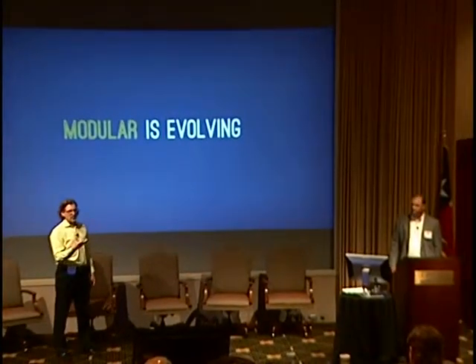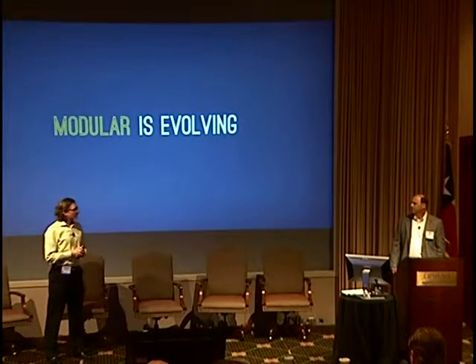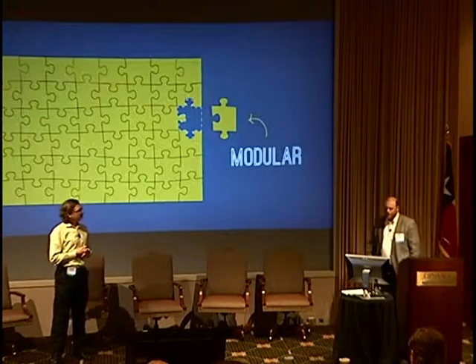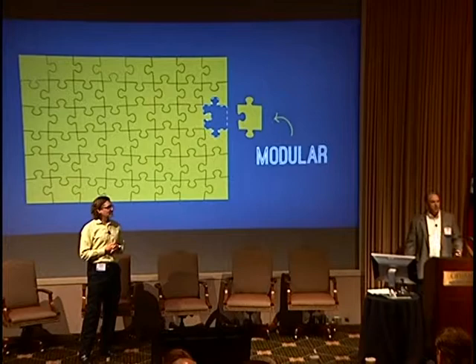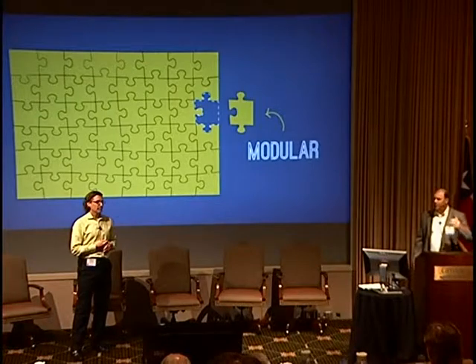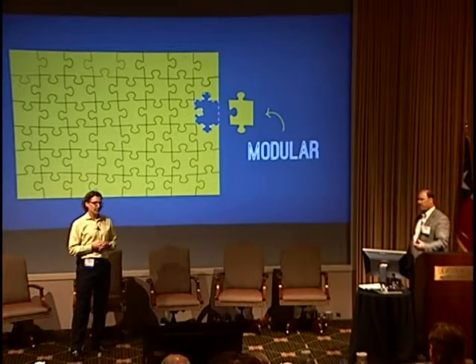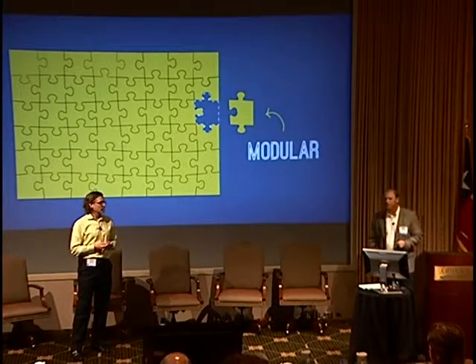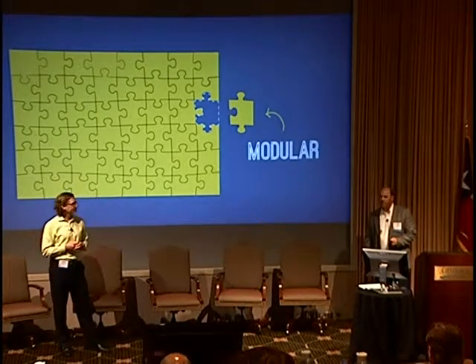It's evolving — there are opportunities for all of us to draw on. ASHRAE's window is expanding and IT hardware vendors are starting to say their equipment will operate in higher humidity environments. But you have to really ask yourself: are you prepared to operate inside a hot, humid data center? There are a lot of issues with humidity causing corrosion and other problems. You need to think twice about chasing that low PUE and how it will affect data center operations. There's still a lot that hasn't changed: supply chain, design, scheduling and planning, procurement, permitting, and site entitlements — modular is definitely a piece of all this and can enhance design and delivery times.